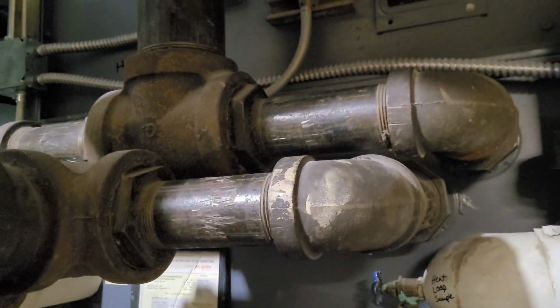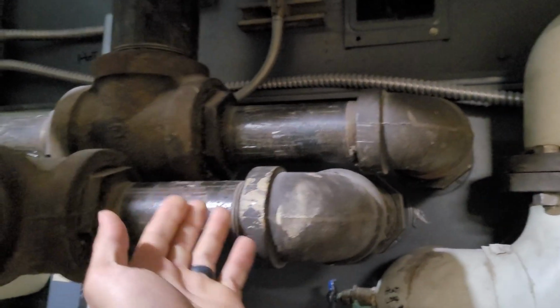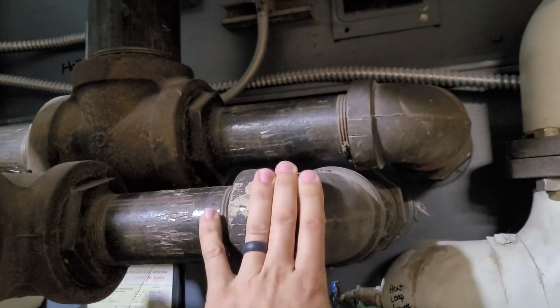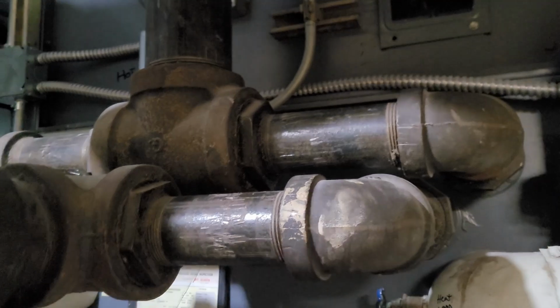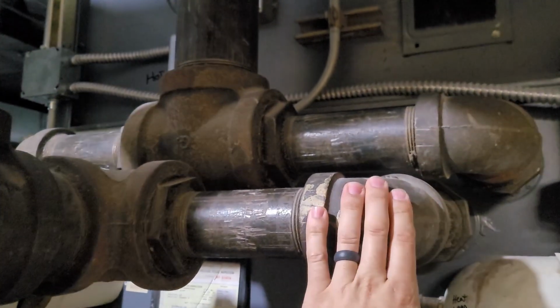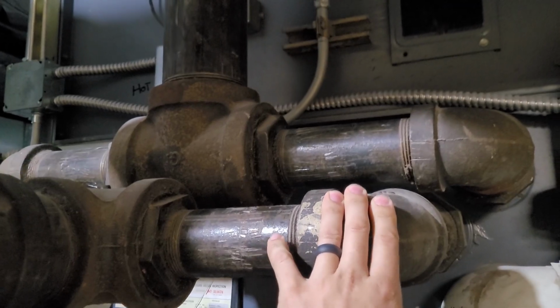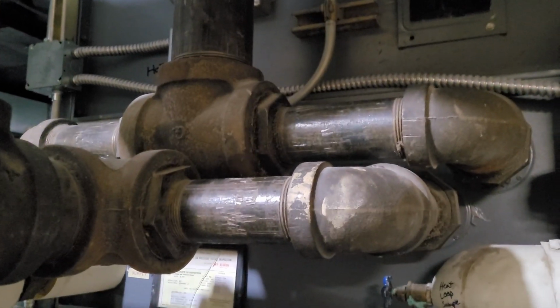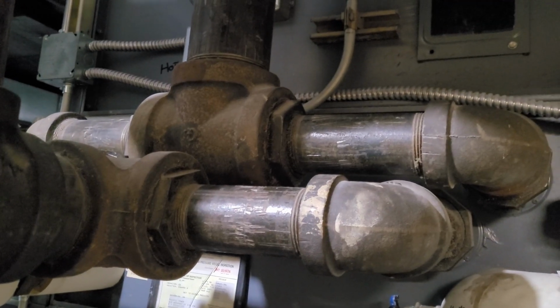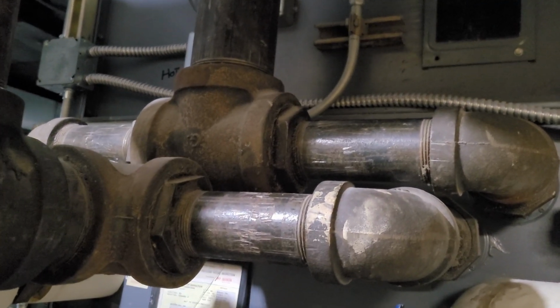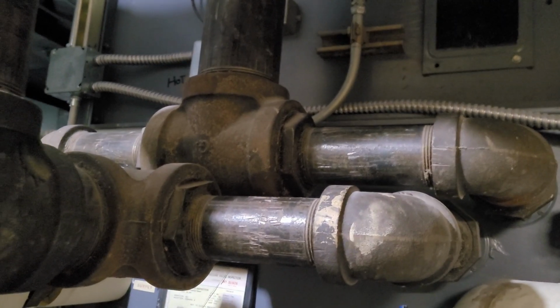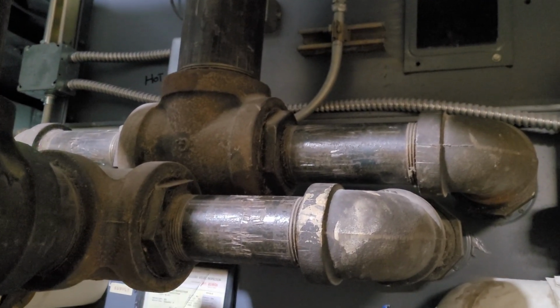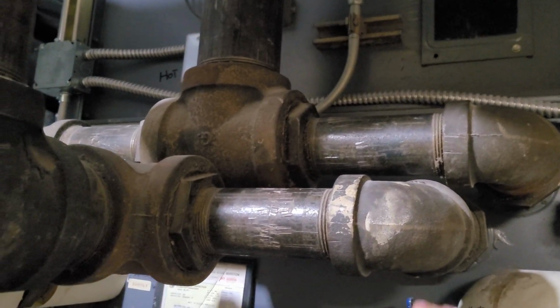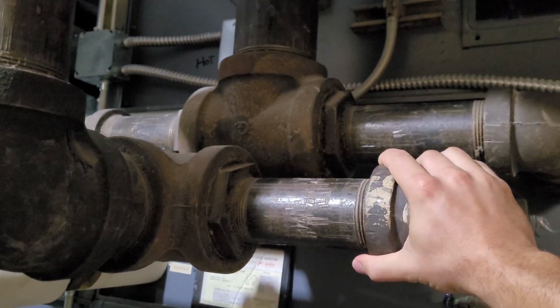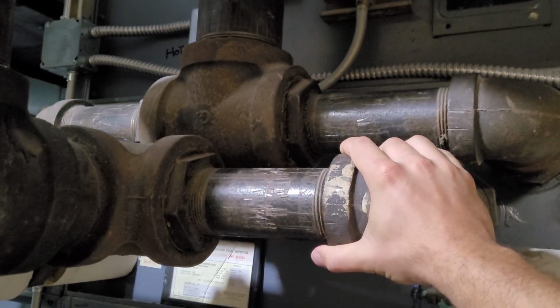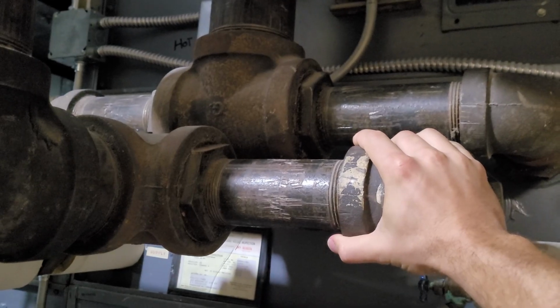here and feeds into the hot deck, or possibly a separate coil, but it's a hot deck coil. So what they can do is, it's like heat recovery. They're taking the condenser water from that chiller when it runs, and during swing season, when you need heating in the morning and cooling in the afternoon, or both heating and cooling at the same time, you can, let's say on a colder day, the exterior of the building might need some heating, and the interior of the building might need some cooling.